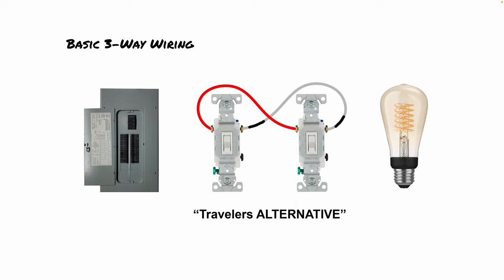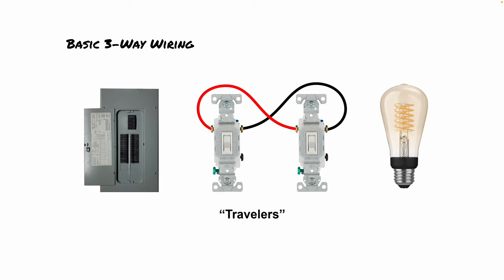The red wire is connected to the left terminal screw on both switches, and the black traveler wire is also connected to the same terminals on both switches. This isn't absolutely necessary for a three-way switch installation to work, but it is best practice to match these up. The reason is that if you ever have a four-way switch — three switches controlling one fixture — mismatched terminals will cause problems. On a three-way install it'll be fine, but ideally match the terminals from one switch to the other.